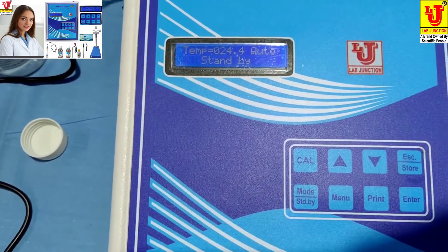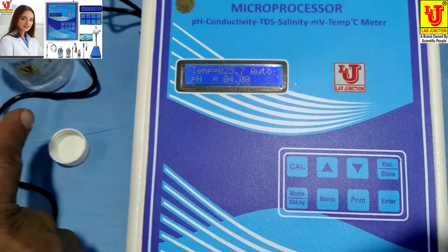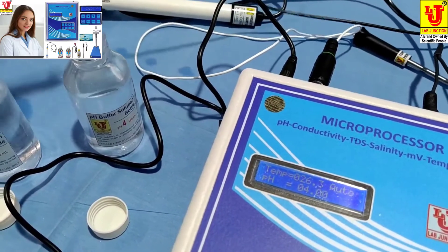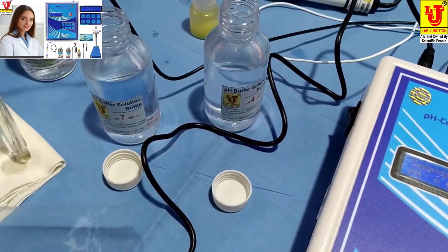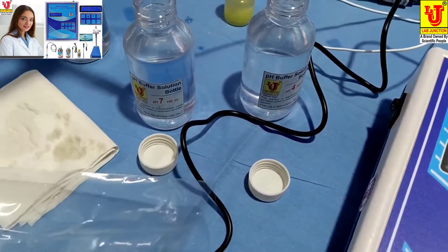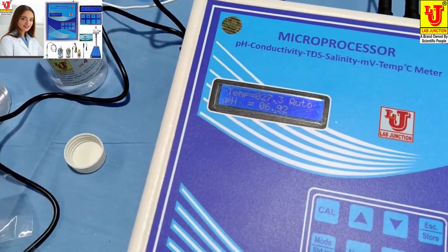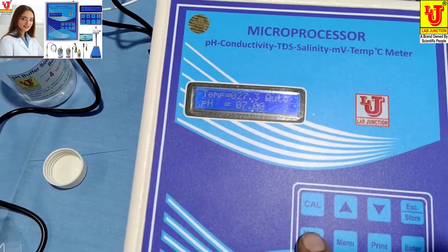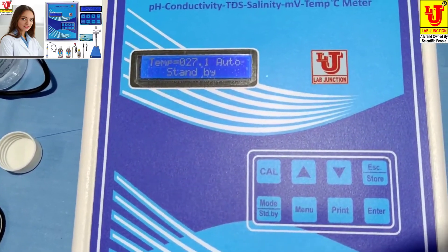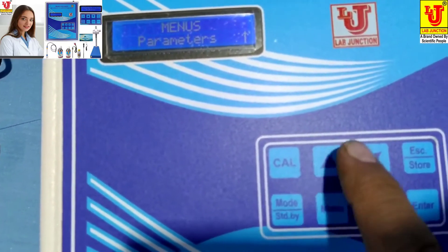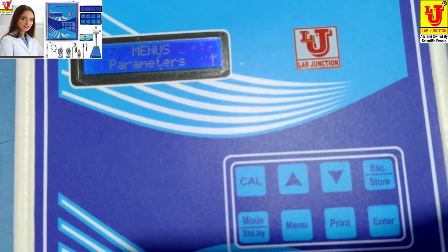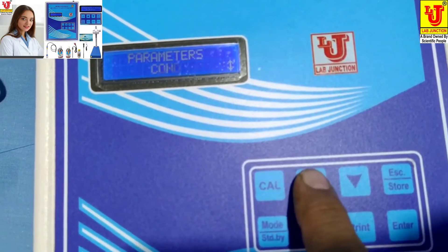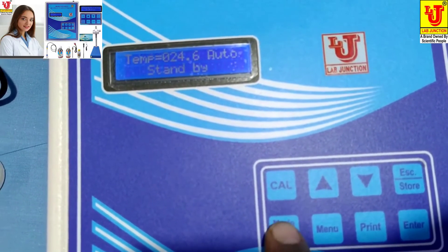pH is now calibrated. You can see the pH result. Currently this is in 4 pH buffer. Now changing to another sample — inserting in 7 pH buffer — it correctly shows 7. Now I am calibrating conductivity. Select conductivity from the menu key, press enter for parameters. This is pH, this is ORP, this is conductivity — press enter. Conductivity is now selected.